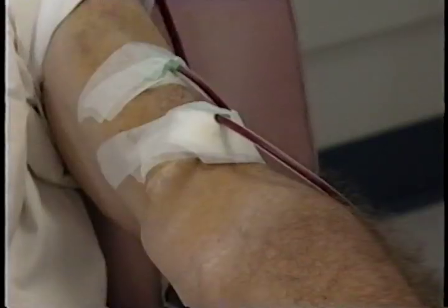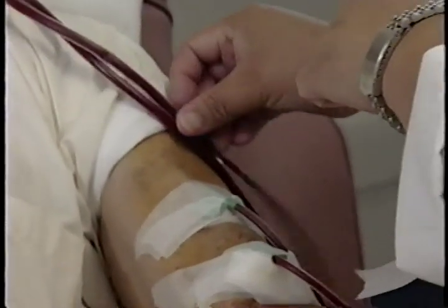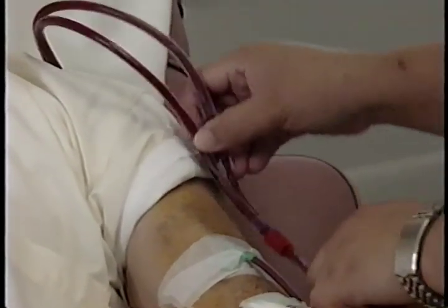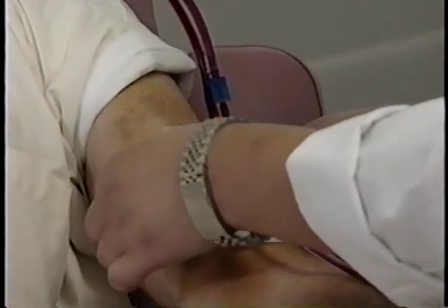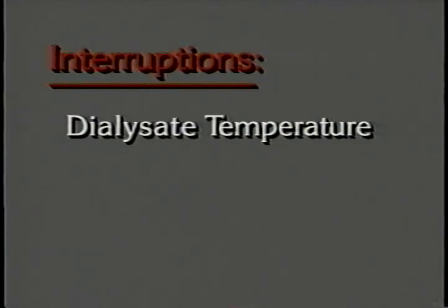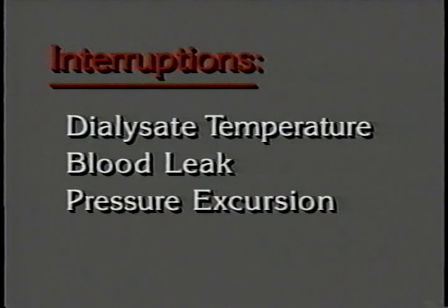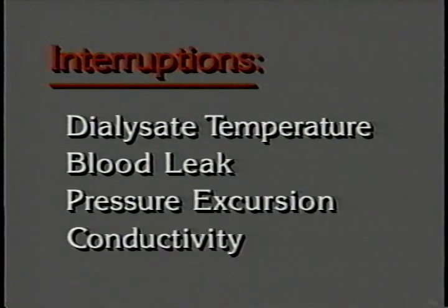There are many reasons for the dialysis treatment to be interrupted, and you may have little or no control over these conditions. For example, if the patient moves and kinks the lines, this may result in an alarm condition that stops dialysis. Dialysis will also be interrupted if the temperature of the dialysate is out of limits, if there is a blood leak, if there is a pressure excursion beyond the set limits, or if the conductivity of the dialysate is either too high or too low. Any of these interruptions will decrease the actual time that the patient is dialyzed.